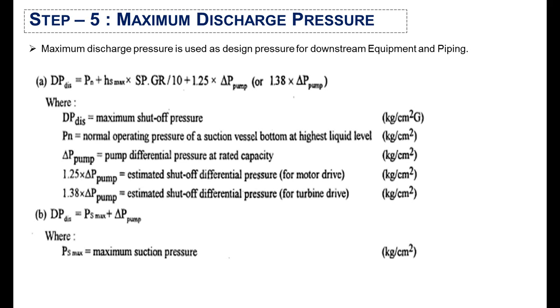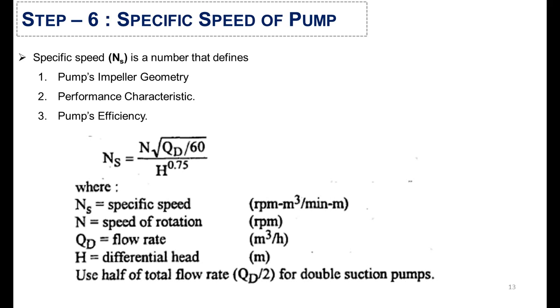In the sixth step, you will calculate the specific speed, which defines the pump impeller geometry, performance characteristics, and pump efficiency. Here is the formula to calculate specific speed, where N is the speed of rotation, Qd is the flow rate at design conditions, and H is the differential head. In cases where there is a double suction pump, we will use half of the total flow rate.